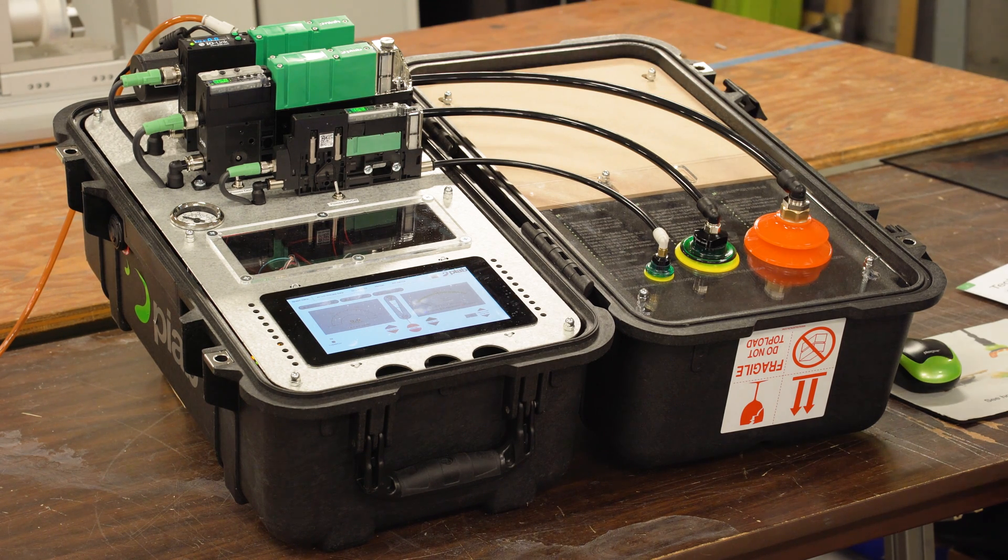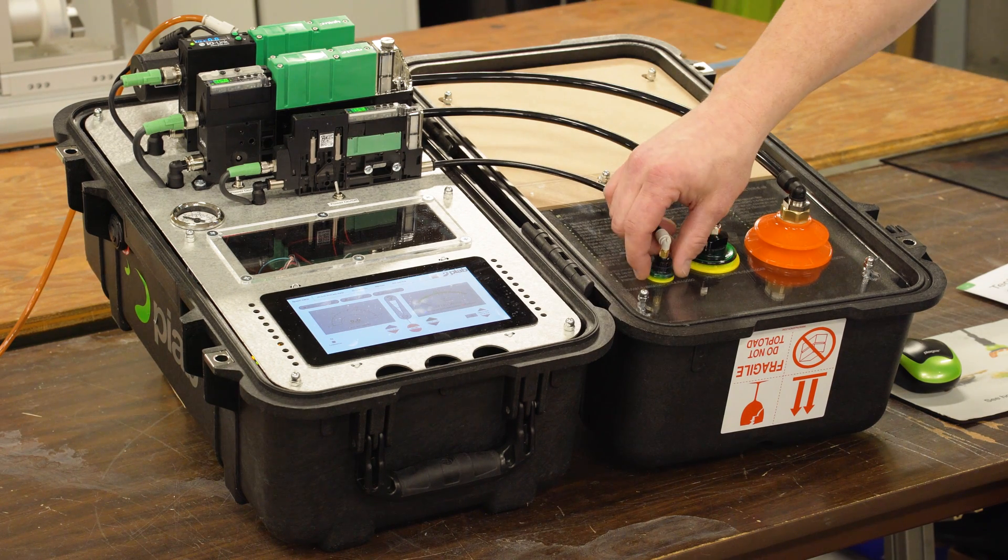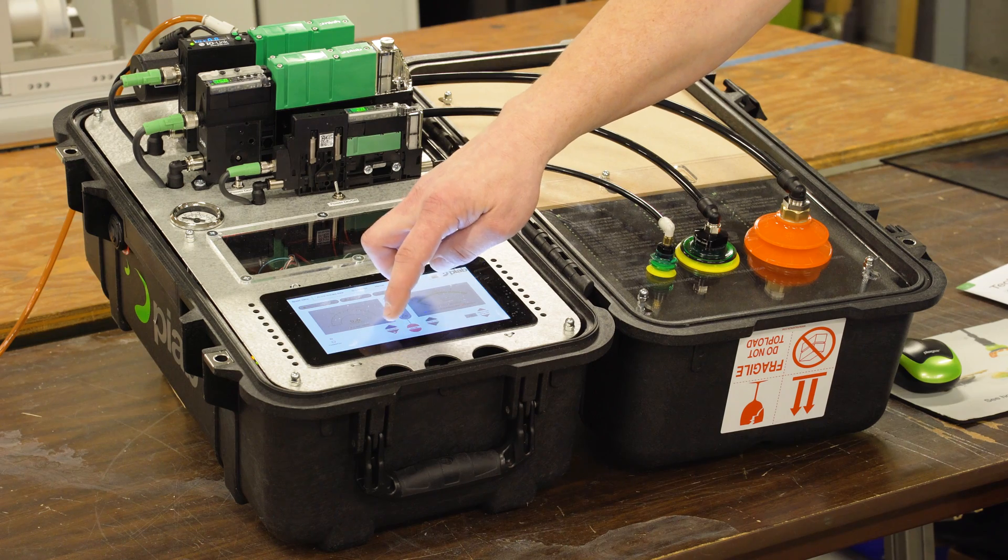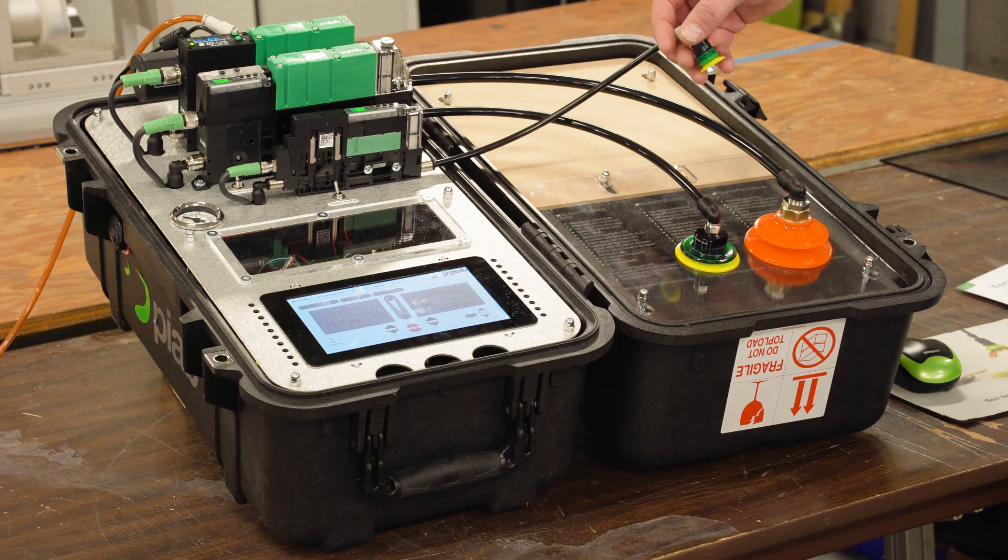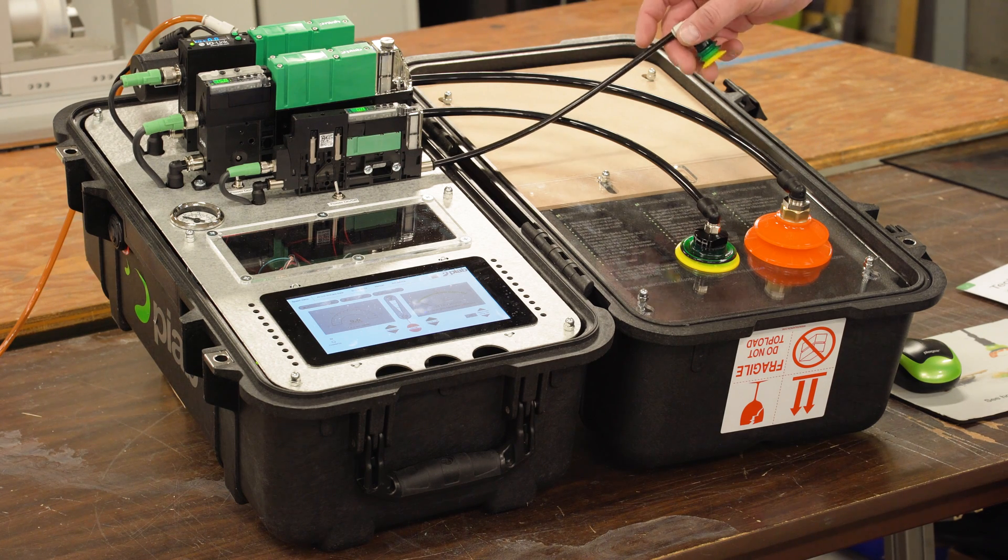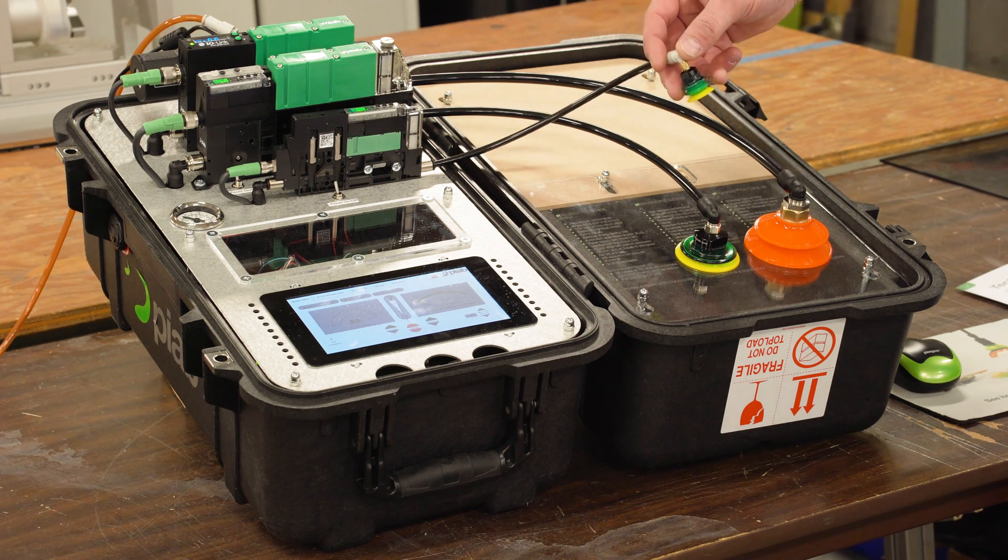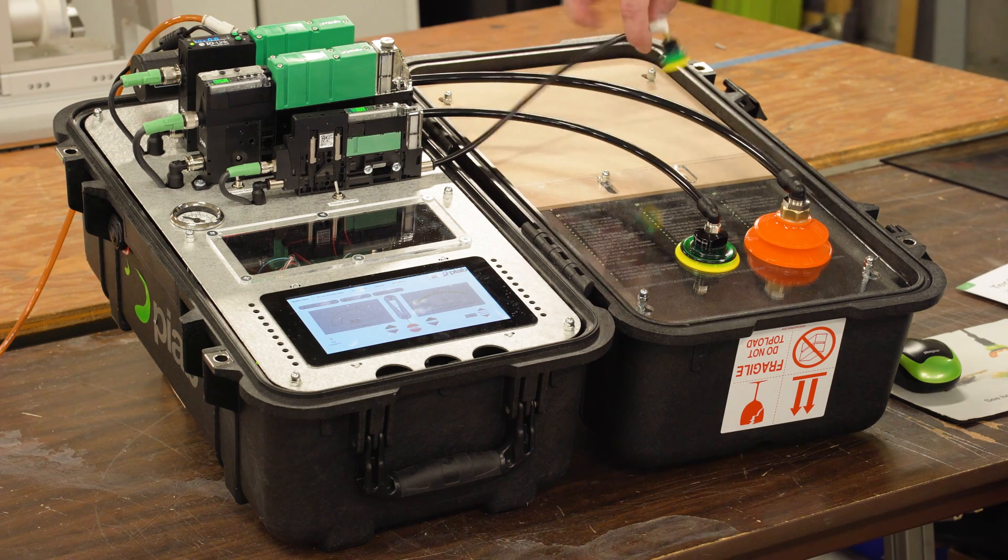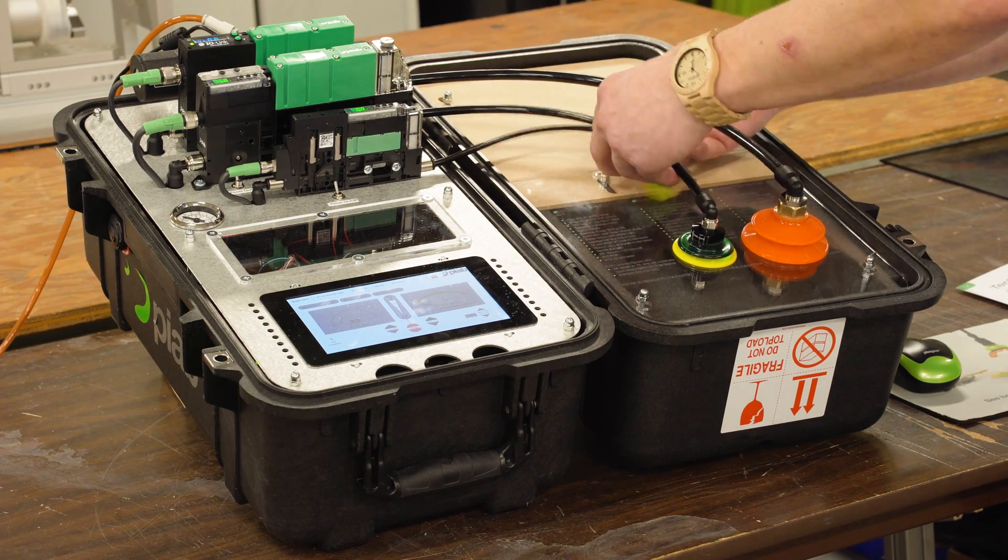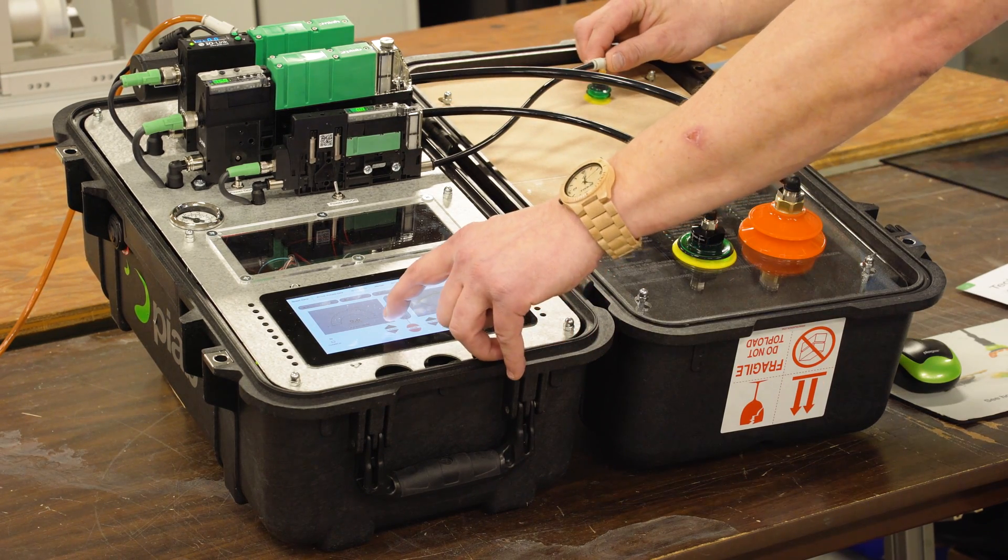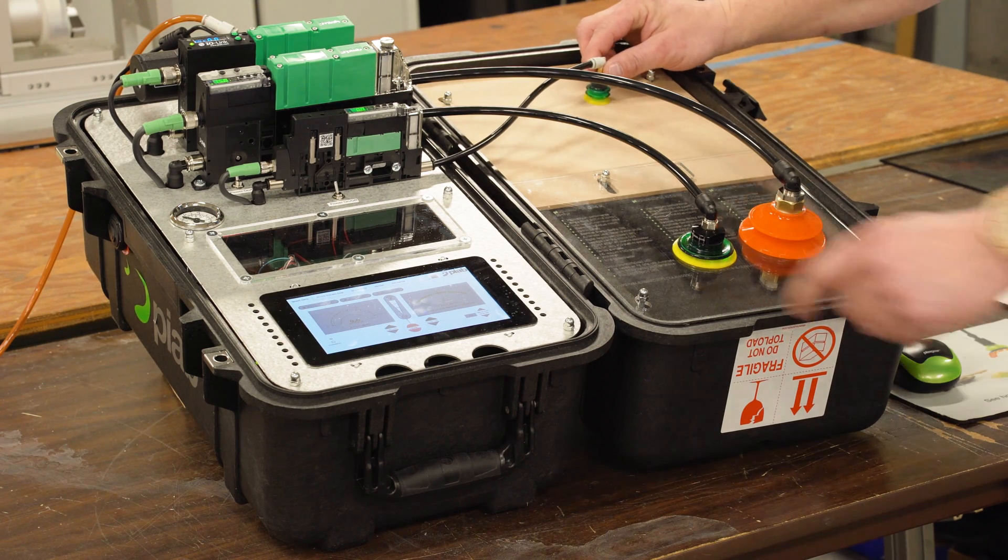So the condition monitoring, how that works, is when you have three, if it reaches the high limit to the low limit three times within five seconds, it automatically switches to staying on constantly. So on this MDF board here, I can demonstrate that a little bit easier. You'll hear it pulse, trigger three times real fast.